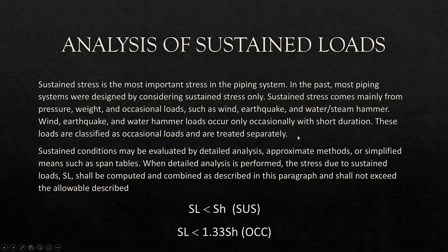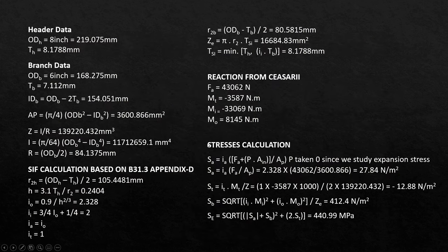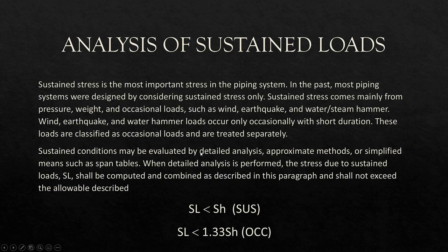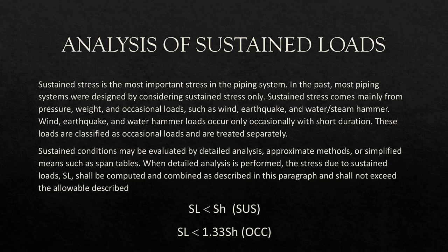Now let's apply the sustained load calculation. The sustained stresses study the effects of pressure and weight, as well as occasional loads like wind, seismic, water hammering, and snow. We first calculate SL, the sustained load. For the sustained load, we compare it to the hot stresses. For occasional loads, we multiply the hot stresses by 1.33 based on ASME B31.3.